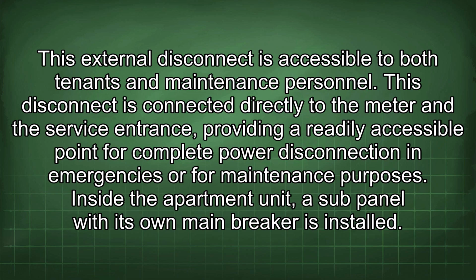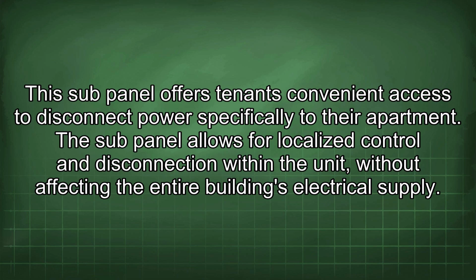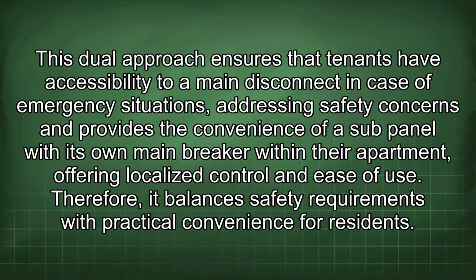Inside the apartment unit, a sub-panel with its own main breaker is installed. This sub-panel offers tenants convenient access to disconnect power specifically to their apartment. The sub-panel allows for localized control and disconnection within the unit, without affecting the entire building's electrical supply. This dual approach ensures that tenants have accessibility to a main disconnect in case of emergency situations, addressing safety concerns, and provides the convenience of a sub-panel with its own main breaker within their apartment, offering localized control and ease of use. Therefore, it balances safety requirements with practical convenience for residents.